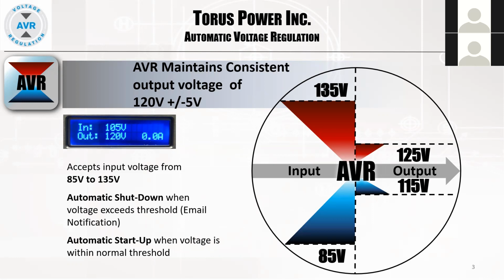So the way that we do that is through a transformer that has multiple input taps. If you think back to the first picture with the transformer, you've got the input winding and the output winding. The length of the input winding and the length of the output winding in relation to each other will determine how much voltage passes on the output. So for example, if you've got a 240 volt transformer on the input side, but you're outputting 120 volts, what people would call a step down transformer, this is done by regulating the size of the output winding compared to the input.